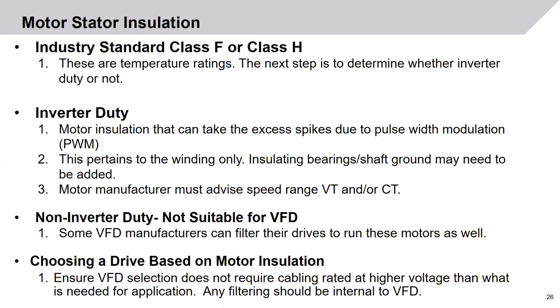How to choose a drive based on motor insulation: the most important thing is to ensure the VFD selection does not require special cabling or special external filtering rated at a higher voltage than the application. Any filtering should be done internal to the VFD, before the motor.